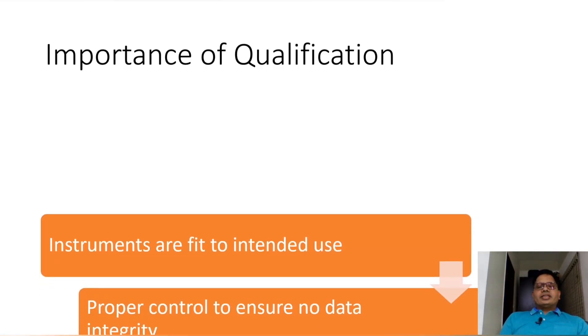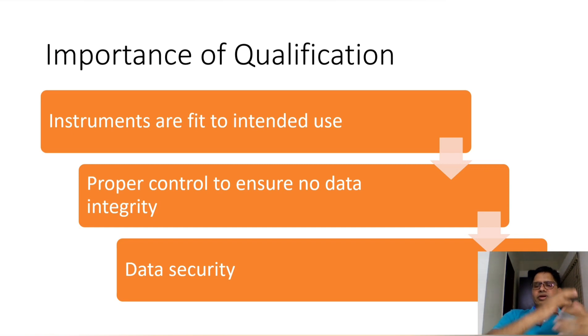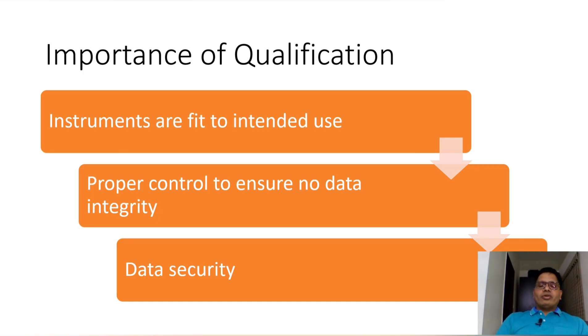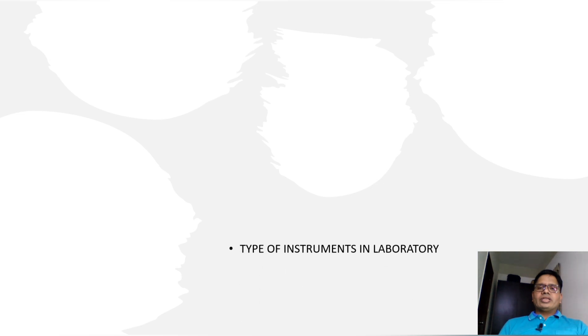The importance of instrument qualification: instruments must be fit for intended use — meaning the purpose for which we procured the instrument. There must be proper control to ensure no data integrity issues. During qualification of all computer systems, we check proper controls to ensure data integrity and data security — that the data generated in the instrument is safe. These three points are very important for qualification.